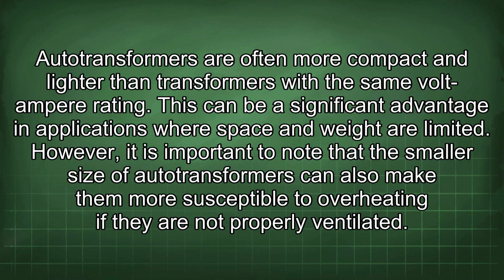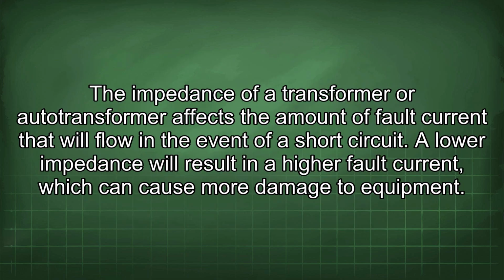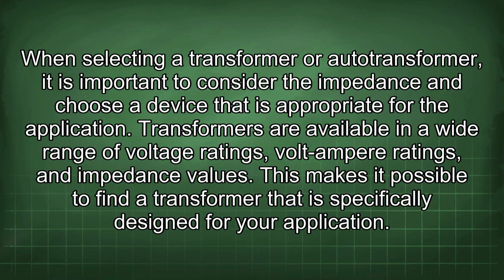However, it is important to note that the smaller size of autotransformers can also make them more susceptible to overheating if they are not properly ventilated. The impedance of a transformer or autotransformer affects the amount of fault current that will flow in the event of a short circuit. A lower impedance will result in a higher fault current, which can cause more damage to equipment.